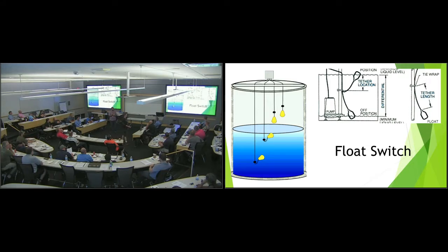The float switch is as simple as it will turn up or turn down. So its shelf state is how you wire it up. You'll typically have normally closed or normally open depending on the operation of what you want to achieve. Sometimes, like with a sump pump, you want to drain all the water out. Other times you want to maintain a level. Does anyone have any questions on how float switches work before we move forward? They'll be part of your project later on.